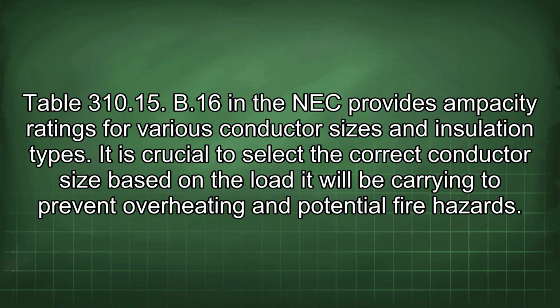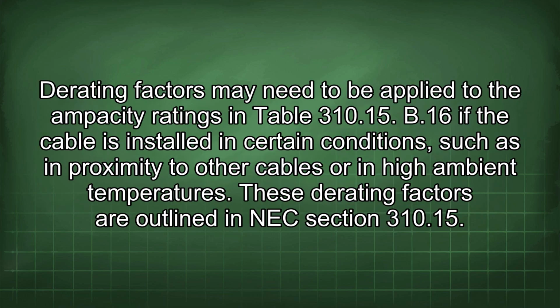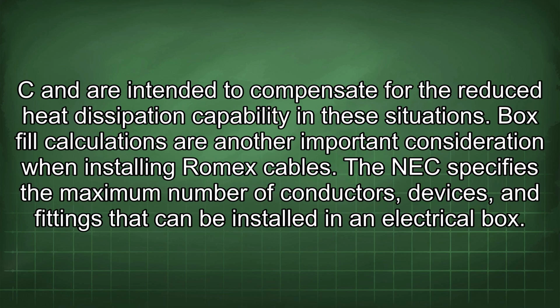B16 in the NEC provides ampacity ratings for various conductor sizes and insulation types. It is crucial to select the correct conductor size based on the load it will be carrying to prevent overheating and potential fire hazards. Derating factors may need to be applied to the ampacity ratings in Table 310.15.B16 if the cable is installed in certain conditions, such as in proximity to other cables or in high ambient temperatures. These derating factors are outlined in NEC Section 310.15.C and are intended to compensate for the reduced heat dissipation capability in these situations.